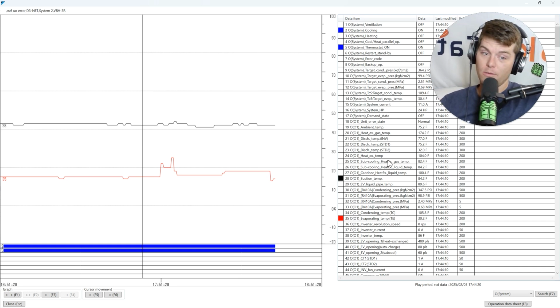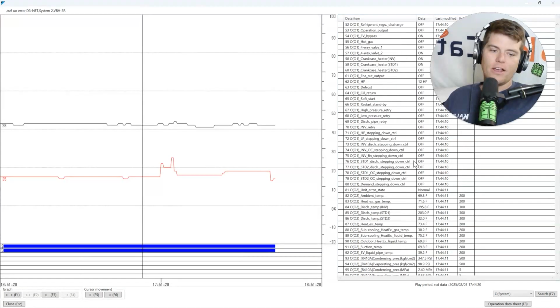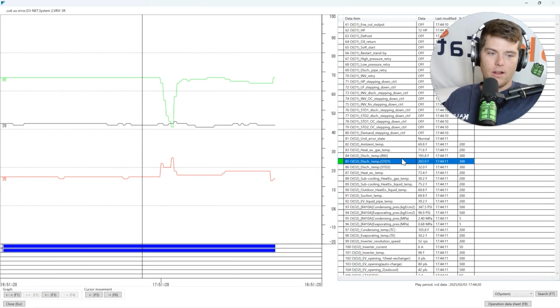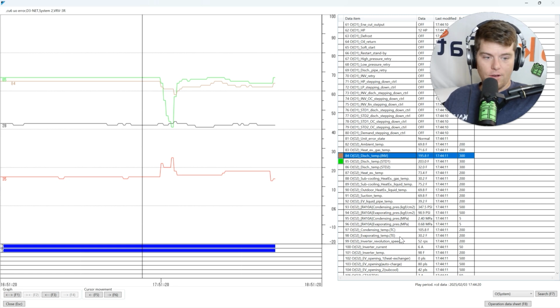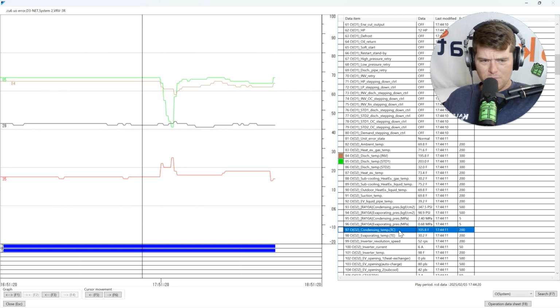What you can correlate to both is high suction superheat, high subcooling, right? High discharge superheat. Those are things that we can measure that mean something every single time, right? Those aren't things that change based upon the mode. That's actually the quality of refrigerant within the system. And so high suction superheat, if I go to my sub module, you'll find that, okay, I've got 2 compressors on now. It is running full bore. And my discharge superheat is, it's not that bad. It's just 105. It's just 203 degree discharge compressor temp. Whatever, right?